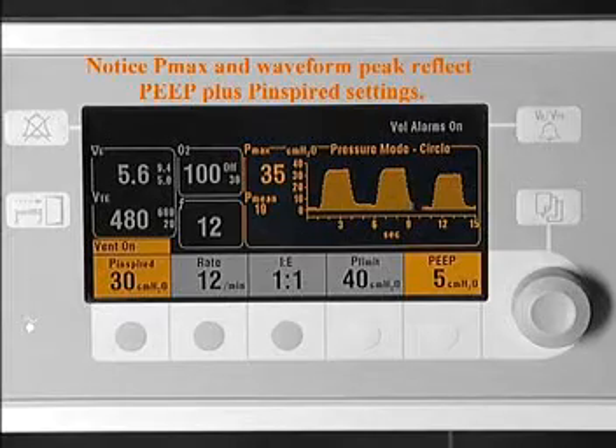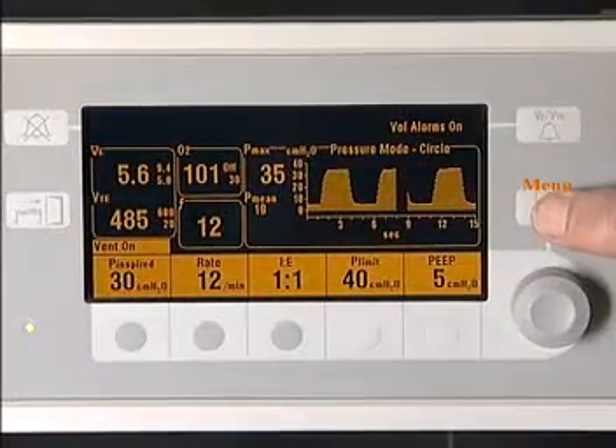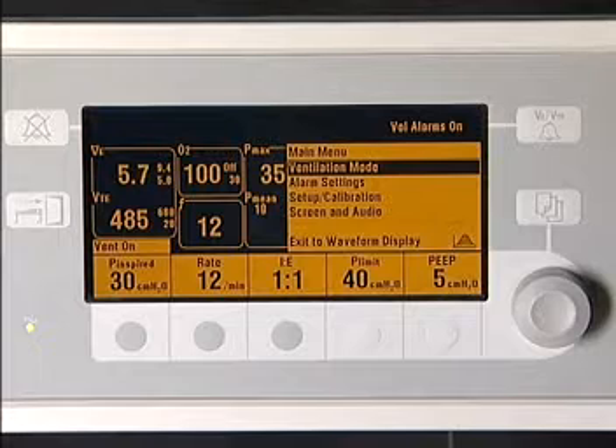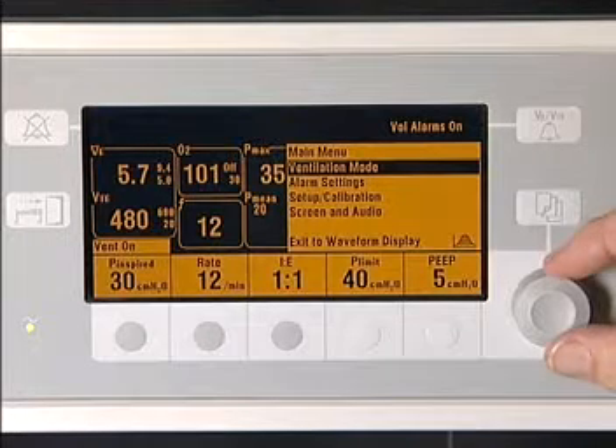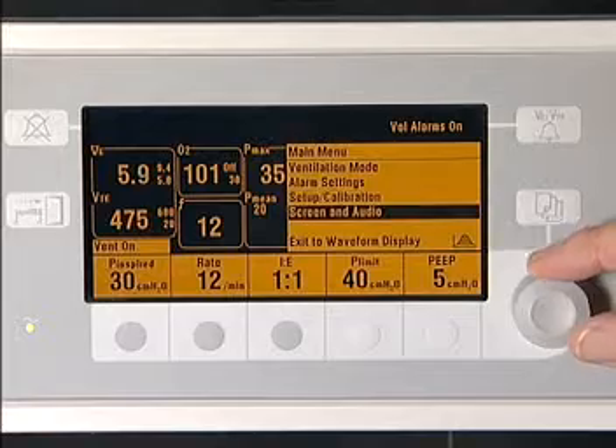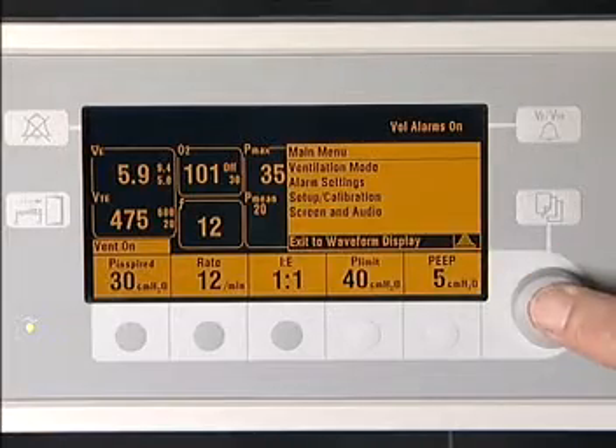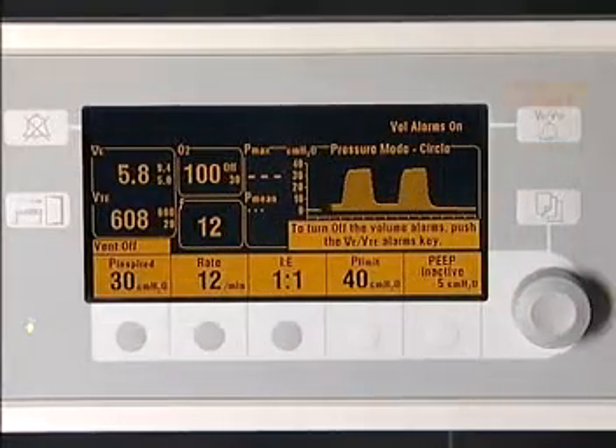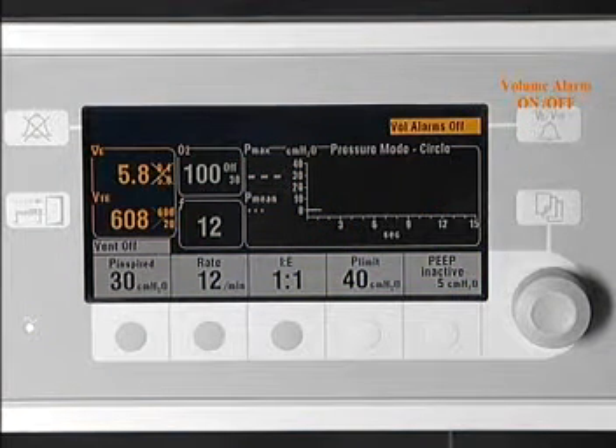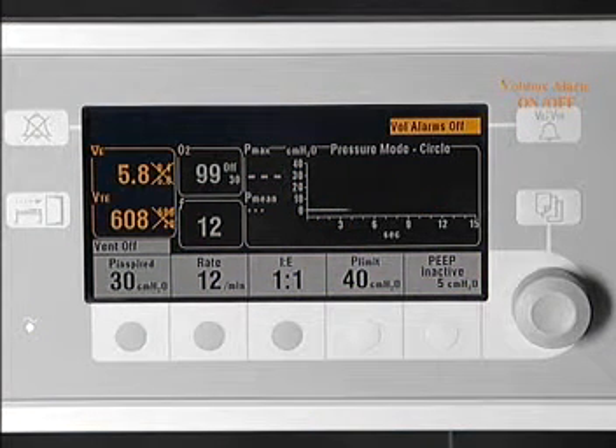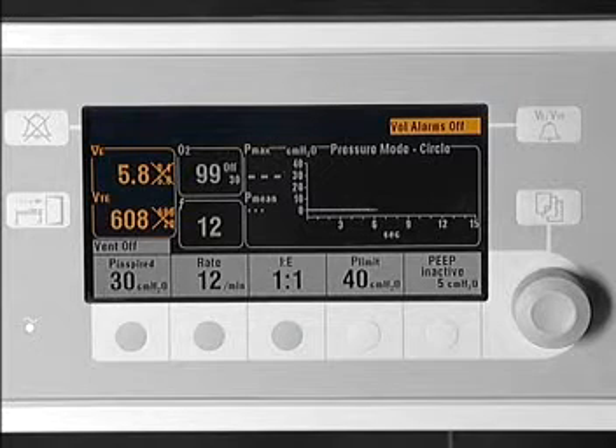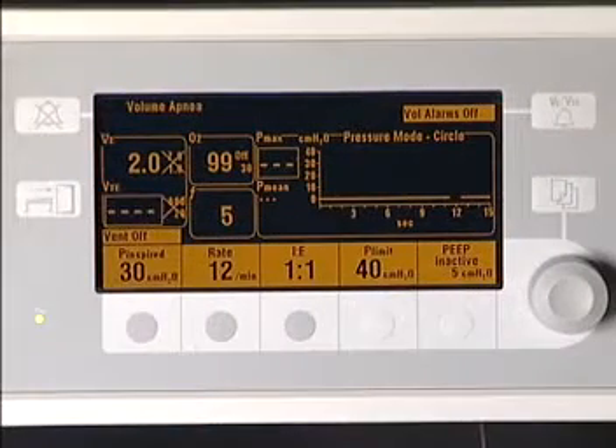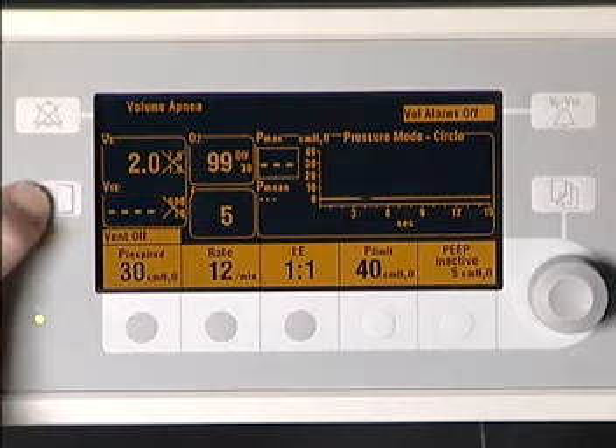Electronic PEEP if desired. The menu key located above the encoder knob allows the user to select the ventilation mode and adjust alarm settings, alarm volumes, screen brightness, etc. The volume alarm key in the top right corner allows the user to silence the alarm tones in the manual ventilation mode if varying tidal volumes and minute volumes are anticipated.